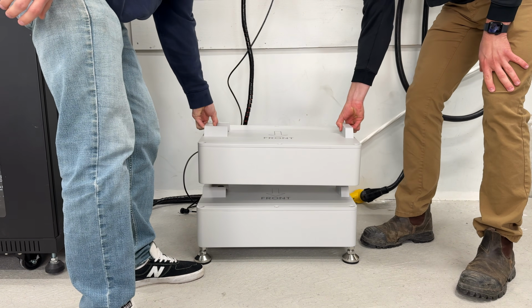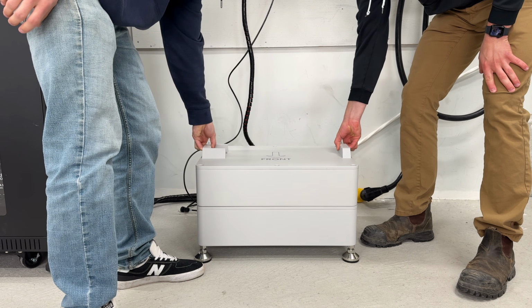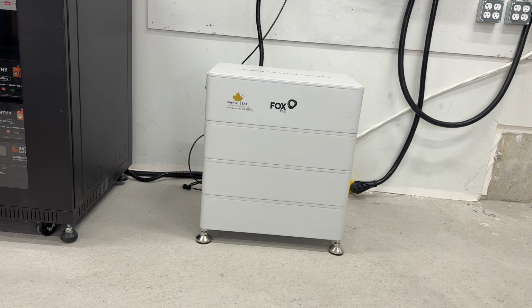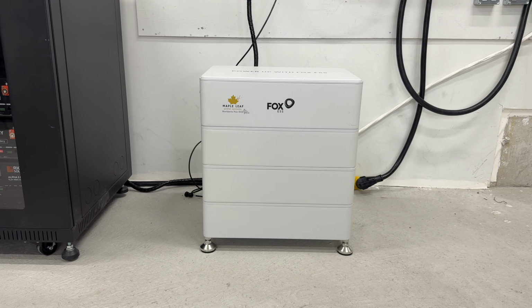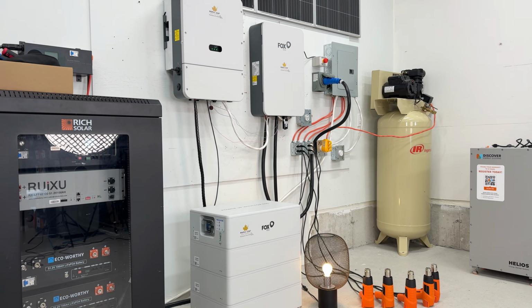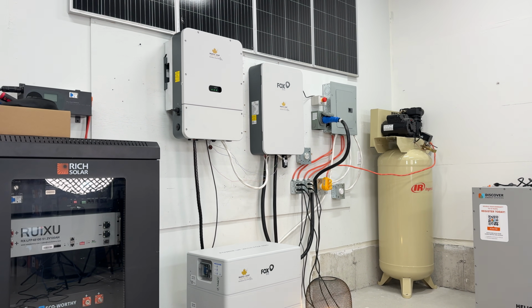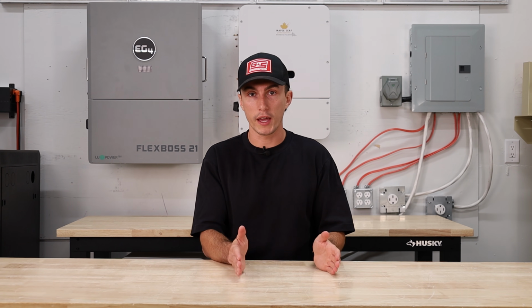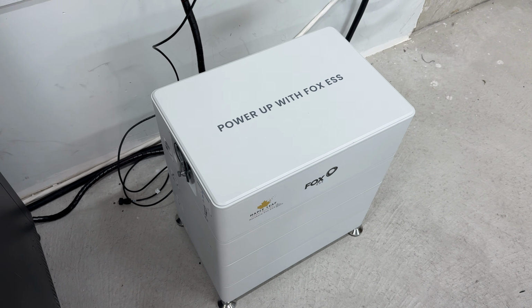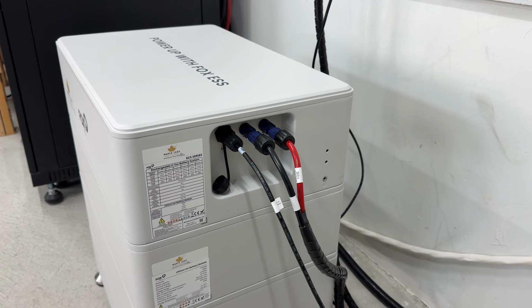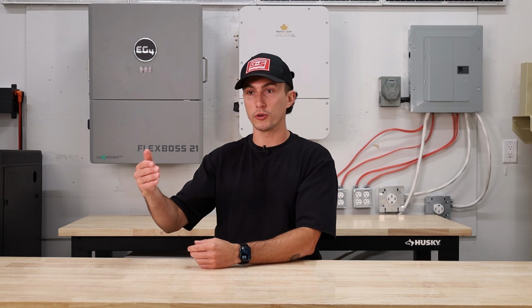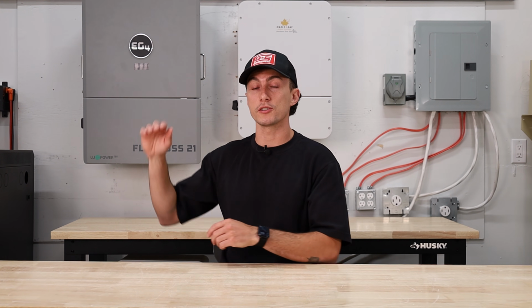With high voltage stuff, it's completely different. As you stack batteries, the nominal voltage increases because high voltage systems put their batteries together in series. So the amperage stays the same, but the voltage increases, and that dictates the output of your entire system. More batteries means higher voltage and higher system output. Basically, with 48 volt, if you have a giant inverter, until you hit the threshold of amperage you'll be less, then it'll be the same. With high voltage, every time you add a battery, your output changes. Eventually you hit a max, but that's the max capacity for batteries. It's not like you hit a threshold and every battery beyond that does nothing. Once you hit that max, you can't even add another battery because your inverter is maxed out.